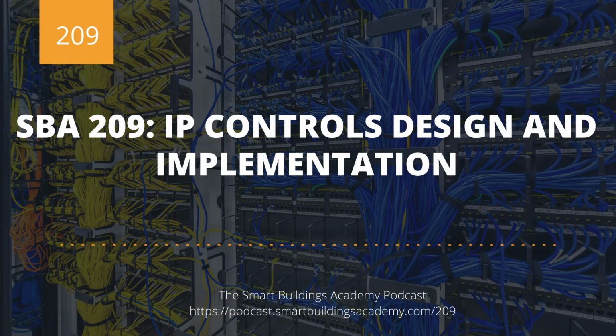You could connect field trunks to them. You could go and run supervisory functions like trends, scheduling, alarm, graphics. They would have web servers, etc. IP controls are the continuation of that plant controller, just filtering down to the other types of controllers.